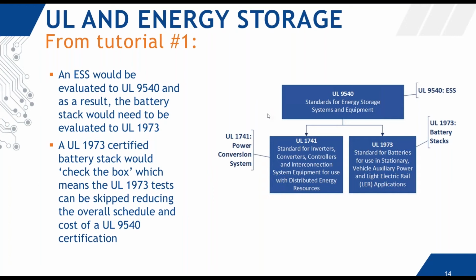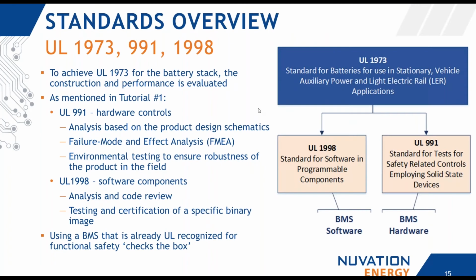And so the chain doesn't really end here. It keeps going. For a UL 1973 certification, there's a construction review and performance testing of the battery stack. As mentioned in tutorial 1, there are two additional standards of interest applicable to a BMS: UL 991, which pertains to the hardware, and UL 1998, which pertains to the software. And they're quite involved standards.